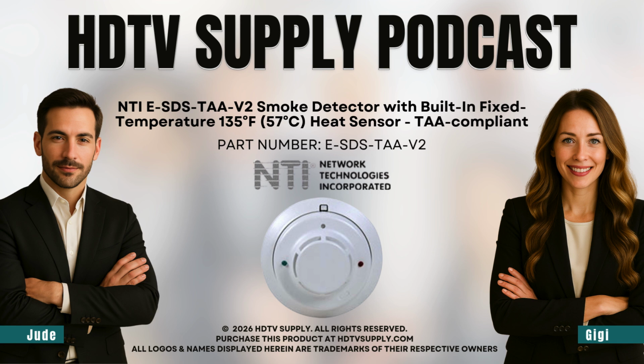Okay, but let's talk about power for a second. It draws power directly from the main EnviroMUX unit. Doesn't that sort of create a single point of failure? If the main unit loses power, all your sensors go dark too. That's a pragmatic question, but you have to look at the power consumption, that's the key. In standby mode, it's sipping just 50 microamps, that's almost nothing, so it's barely putting any strain on the main unit's UPS system if the facility power goes out. It maximizes the monitoring runtime, but when an alarm actually triggers, it jumps to 20 milliamps. That's a massive difference, a very clear, unambiguous signal. So that efficiency really defines its operational integrity.